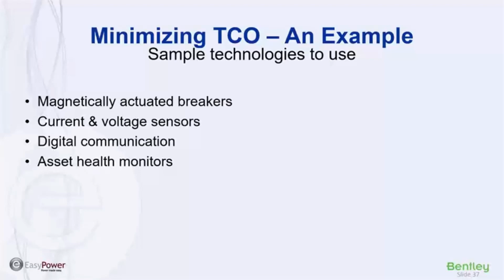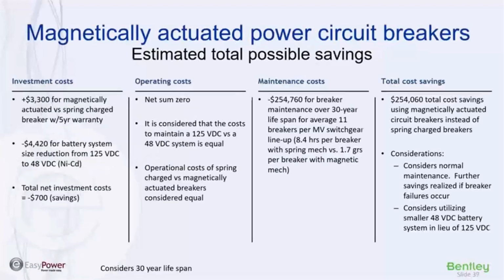So if you look at magnetically actuated circuit breakers, right? Essentially, this is the technology that takes care of your spring mechanism, and it's a very simple mechanism. It has very minimal maintenance requirements. So typically a spring manufacturer's recommendation would be to maintain or service the mechanism every year, right? In case of a magnetically actuated breaker, we recommend nothing less than 5 years. So it's an extended period.